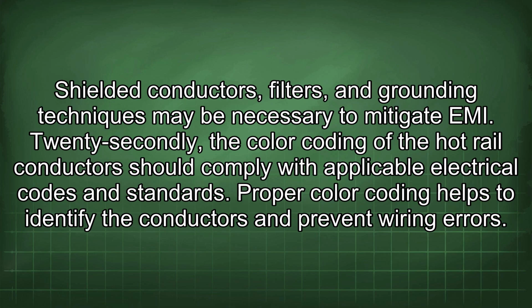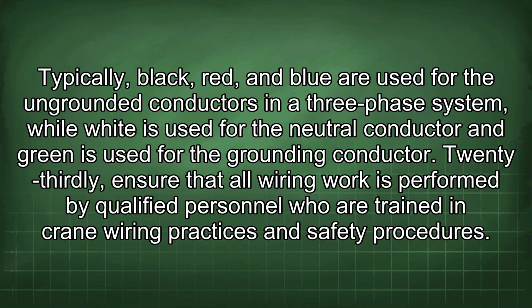22ndly, the color coding of the hot rail conductor should comply with applicable electrical codes and standards. Proper color coding helps to identify the conductors and prevent wiring errors. Typically, black, red, and blue are used for the ungrounded conductors in a three-phase system, while white is used for the neutral conductor and green is used for the grounding conductor.